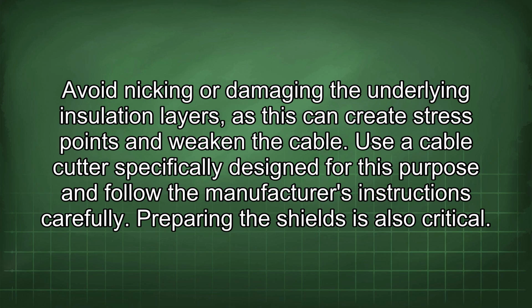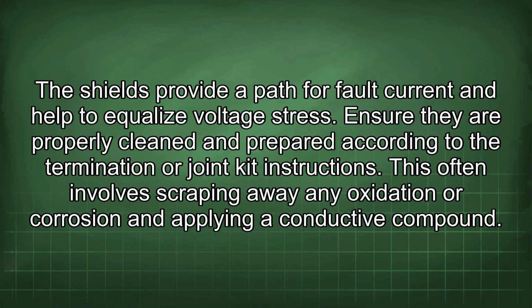Use a cable cutter specifically designed for this purpose and follow the manufacturer's instructions carefully. Preparing the shields is also critical. The shields provide a path for fault current and help to equalize voltage stress. Ensure they are properly cleaned and prepared according to the termination or joint kit instructions. This often involves scraping away any oxidation or corrosion and applying a conductive compound.